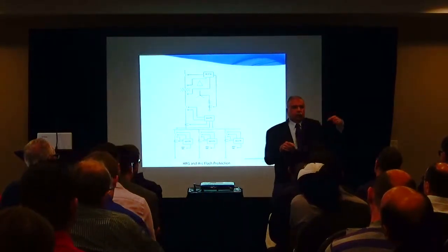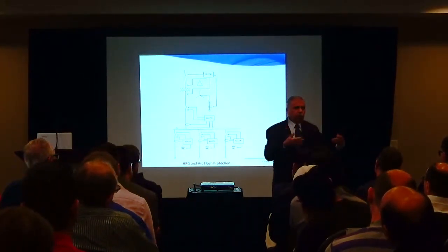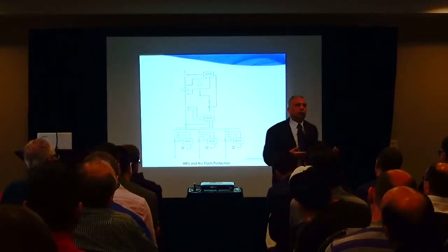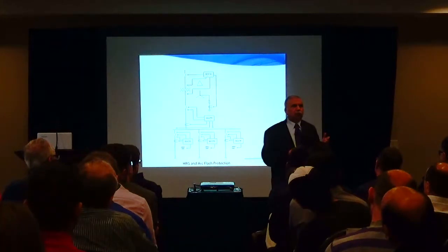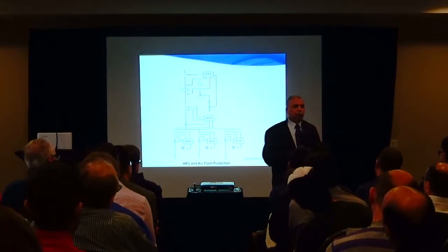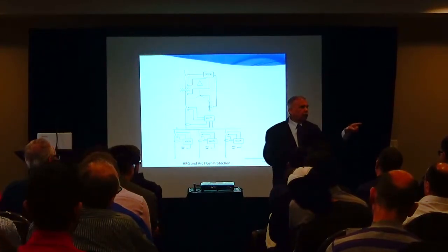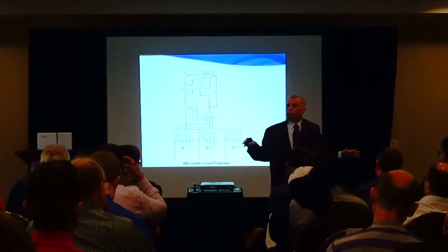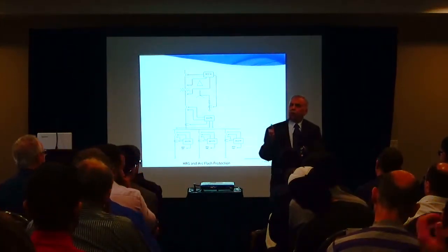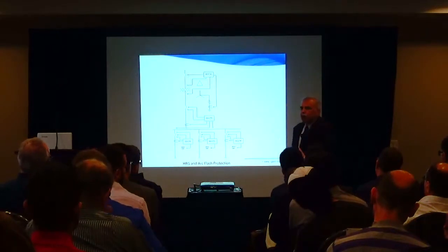And each of these was a medium voltage input to the incoming unit substation in those buildings to serve the building load. And they said, well, we often have to go to this primary side and we need to deal with this, including the transformer terminal box on both sides. They were okay on the unit substation from the secondary breaker all the way down in the distribution. The calories were manageable, but on the line side of the main breaker, they had a problem.